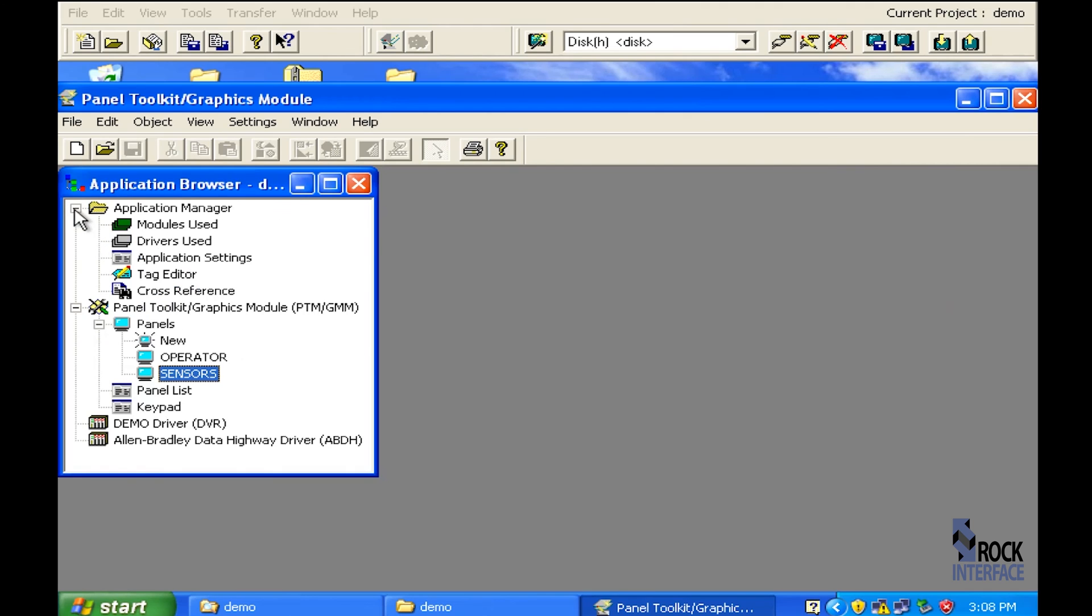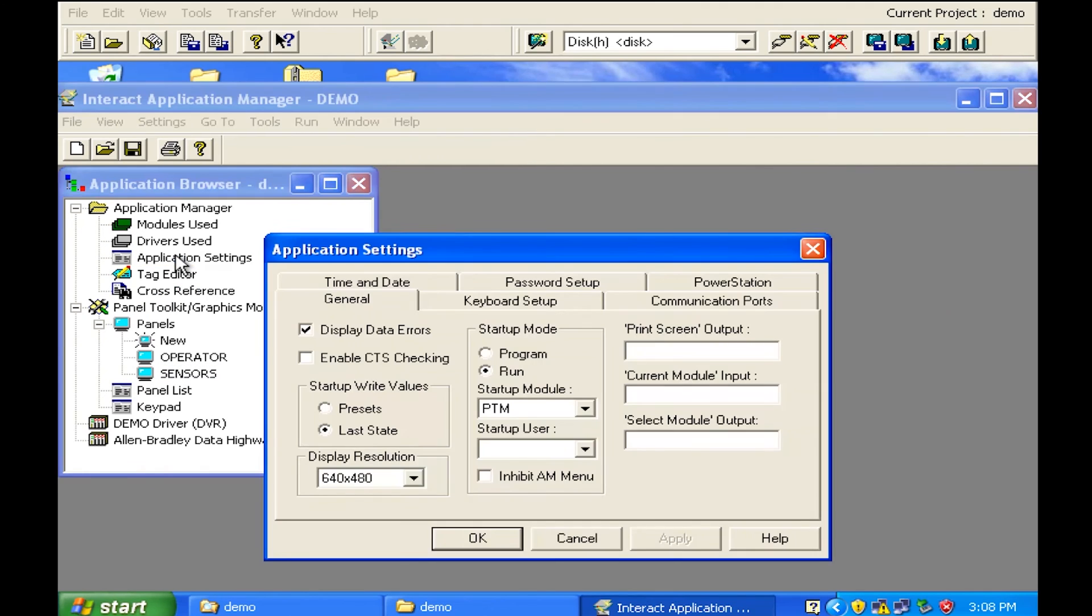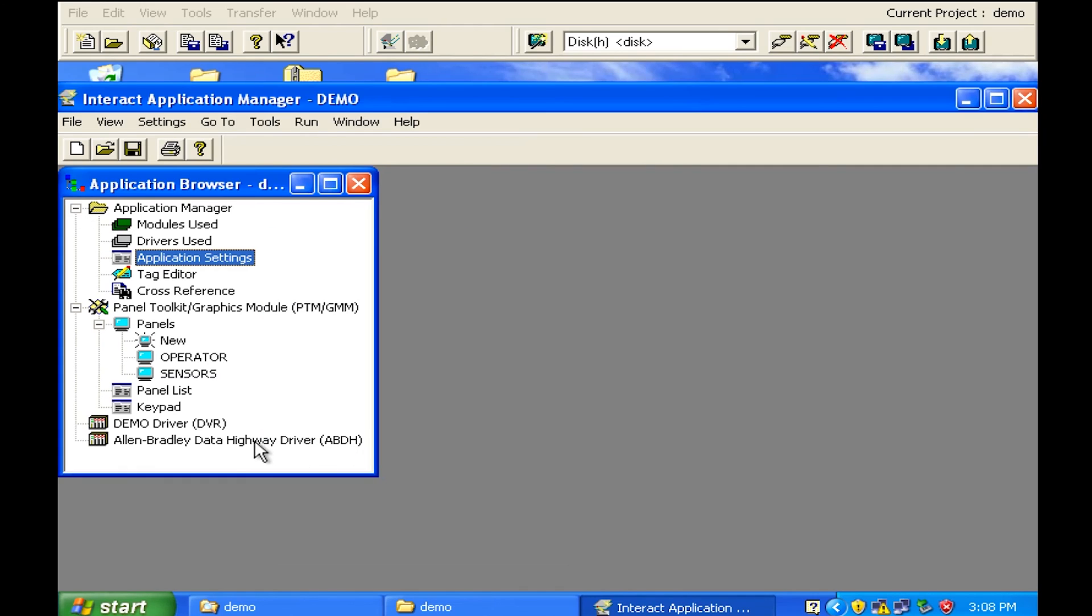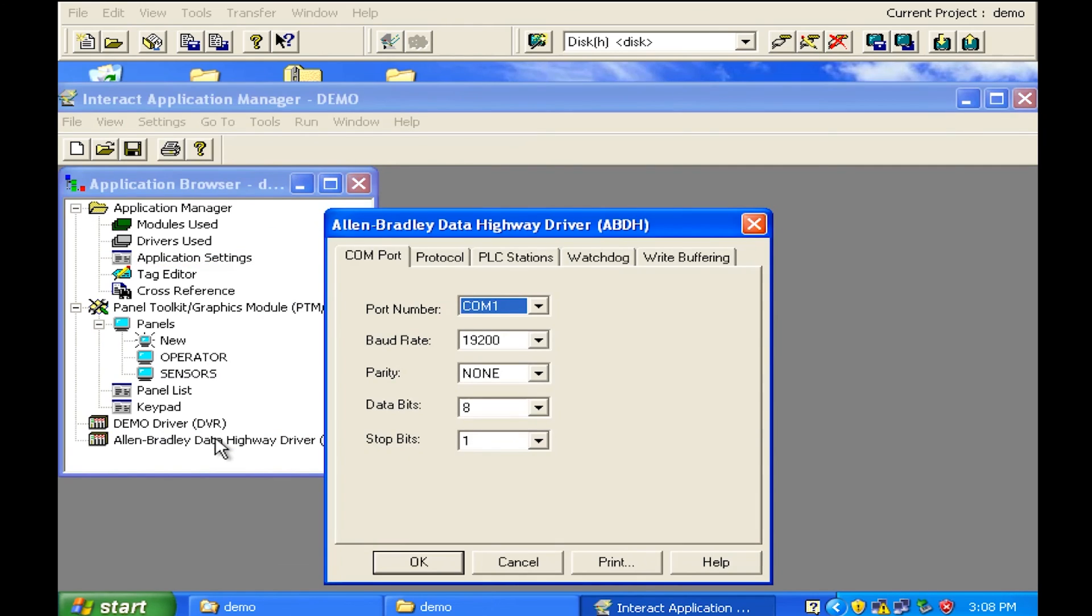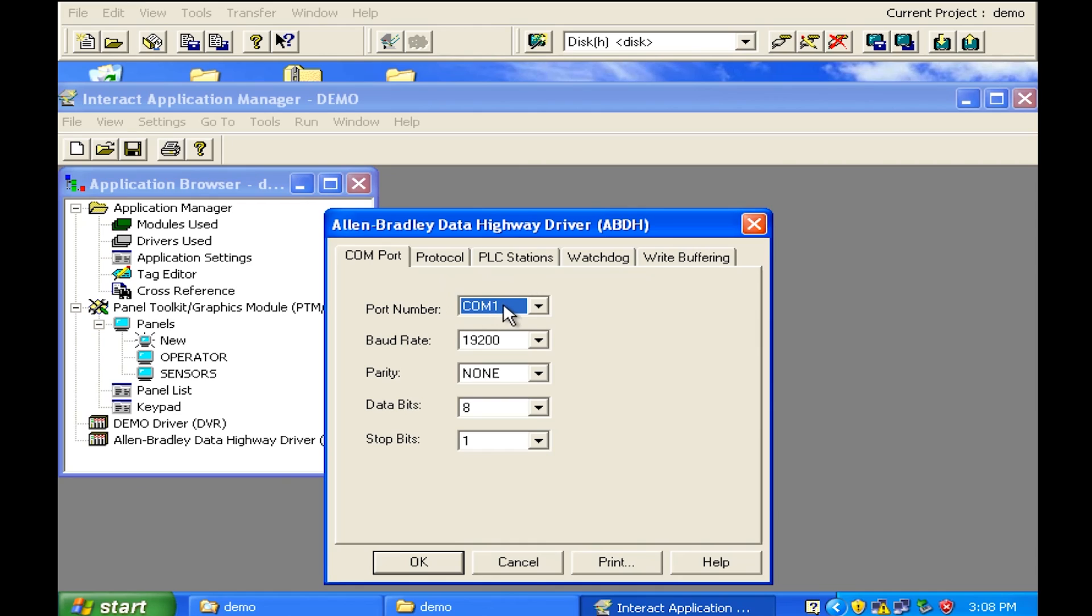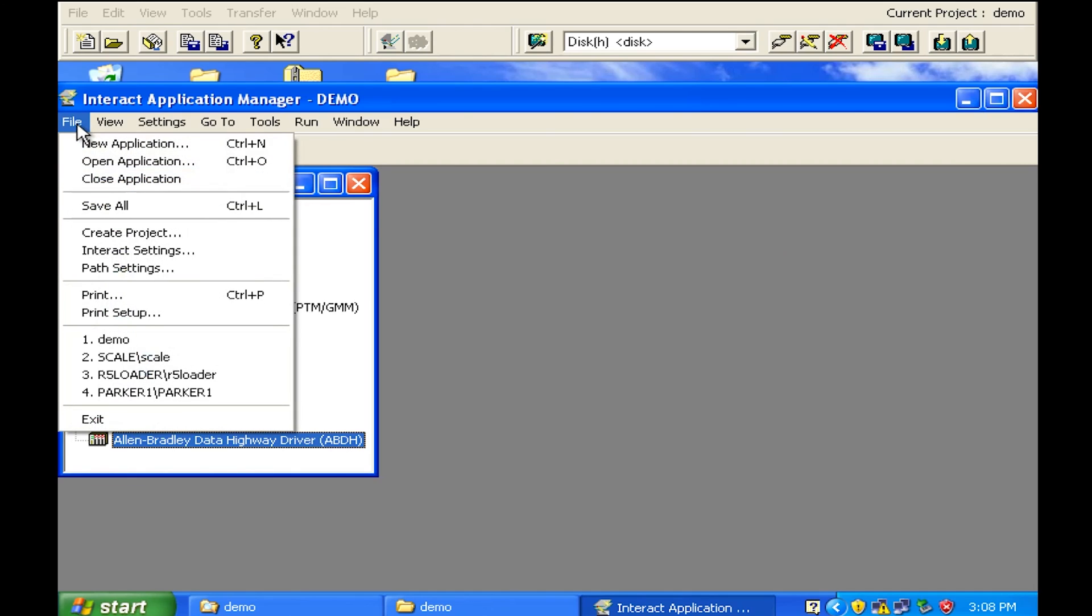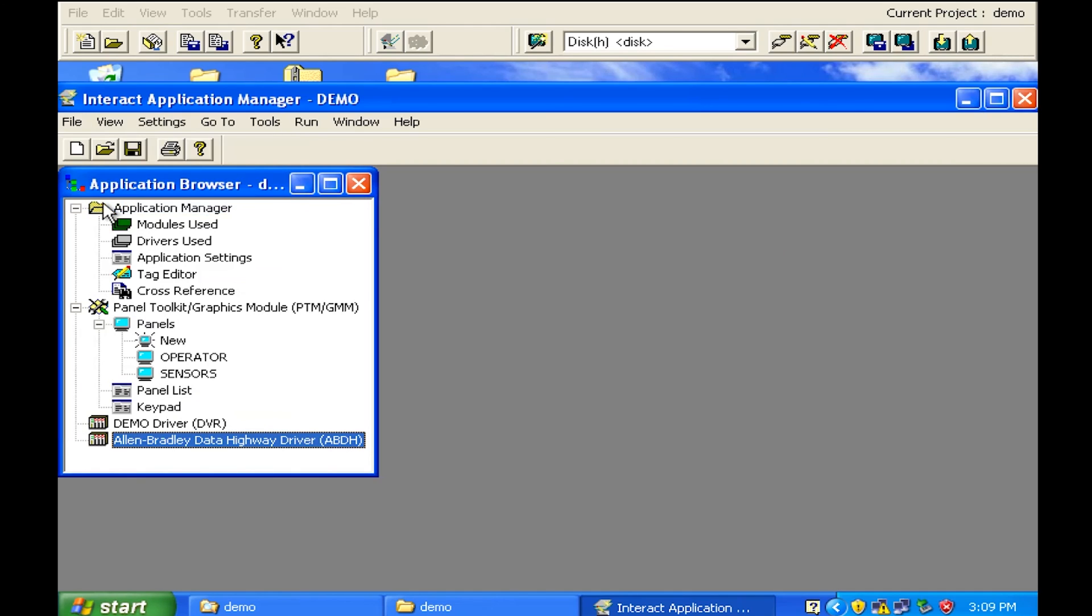You want to go ahead and take a look at some of the application settings. But you also can go in and take a look more importantly to see how the PLC was set up to confirm to make sure you've got your power station configured correctly to talk to the PLC. In this instance looks like they were using COM1 and talking serial using Allen Bradley Data Highway Plus. And then I go over here to file and save all.